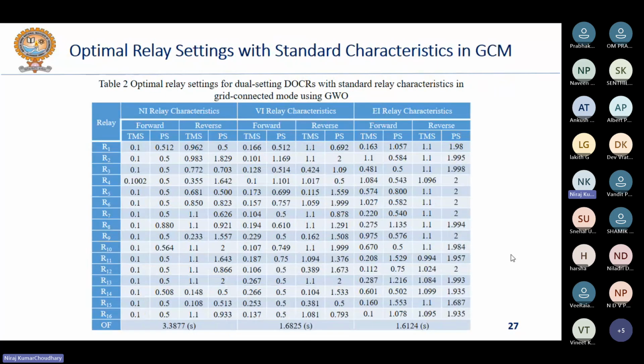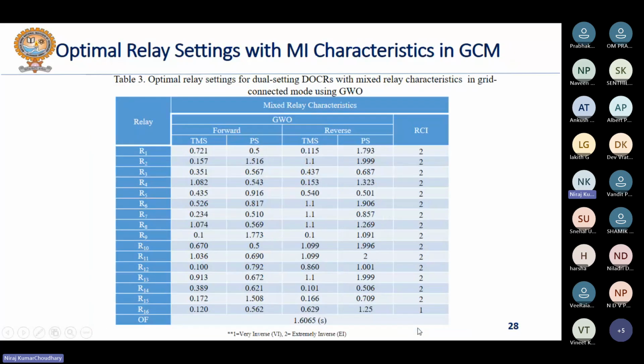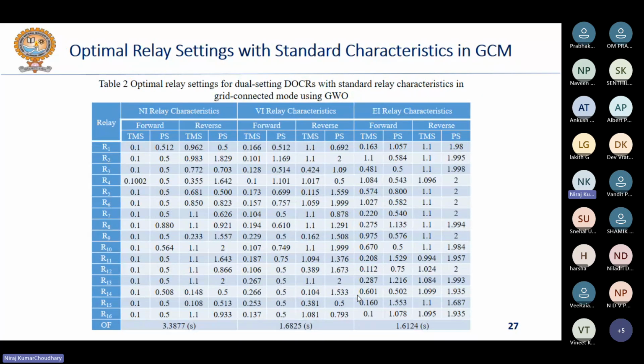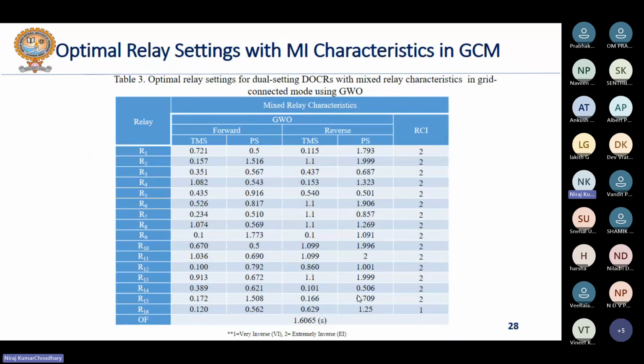So this is again less than the total time of operation of the relay that we calculated in the case of extremely inverse characteristics. It was 1.6124 second, and here it is 1.6065 second. Now anyone can say, what is the big deal in that? Here you are getting 1.6124, here you are getting 1.6065. The magnitude is not that much different, but it is very significant for this particular problem, because you know that practically the relay operation time on the occurrence of a fault should sometimes be in milliseconds also, right? That's why it is of that much relevance.